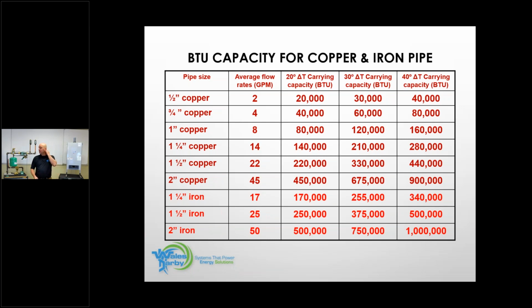I mean, snow melts, they start at 25. Right, there you go. Bigger, we want to go to a 30 to keep pipe size as small as possible. Yeah, right. So again, this is best practice. This is not for every single install. Radiant, we said we design for 10. That's if I'm in your living room, I'm designing that for 10. Jim's doing the design for a snow melt, it's going to start at 25. Or you're going to end up with 2-inch pipes in your driveway to melt the snow. That's just not practical. So that's where this comes from.